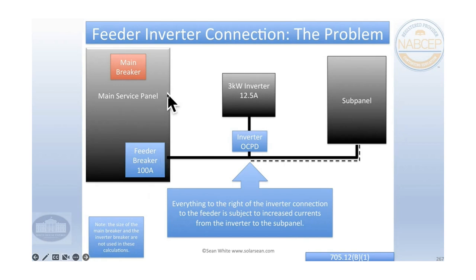So first of all, what we're talking about here is connecting to a feeder. So it's not a supply side connection because there is a breaker in front of it, and you've got this feeder here, and then all of a sudden you're adding an inverter, you're adding a power source. And what you have to do for the calculation here is you take the feeder breaker current plus 125% of the inverter current, and then you have two things that you can do.